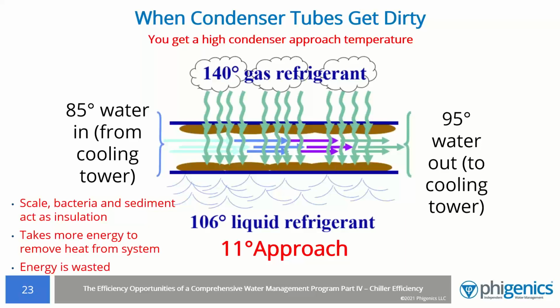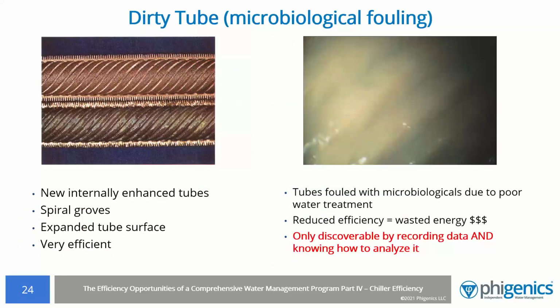Next slide. Now, over the last 20 or 25 years, a lot of manufacturers, or all the manufacturers, have improved chiller efficiencies by going to what they call internally enhanced tubes. On the interior of the tube, it used to be smooth bore throughout. Now, with this enhancement, it turbulates the water. You get much more turbulence in the water. You get much better heat transfer effect between the tube and the water. But it also provides an opportunity for fouling.